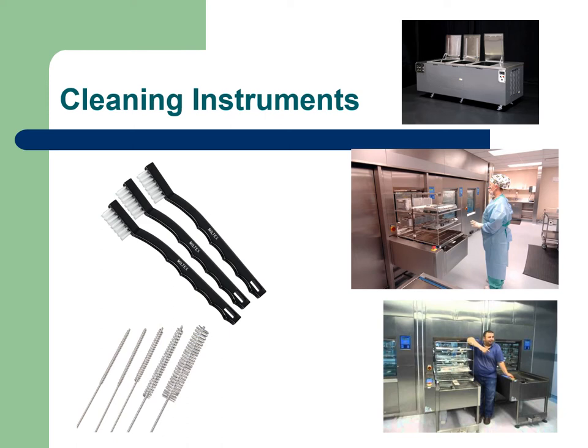Something else they might do in addition to hand cleaning is put them in the ultrasonic washer, shown on the top right. This ultrasonic cleaner works by a process called cavitation - because of the high frequency ultrasonic waves used in the device, tiny bubbles are created in and around and on the instruments, and as those bubbles burst or explode, they push out the debris.